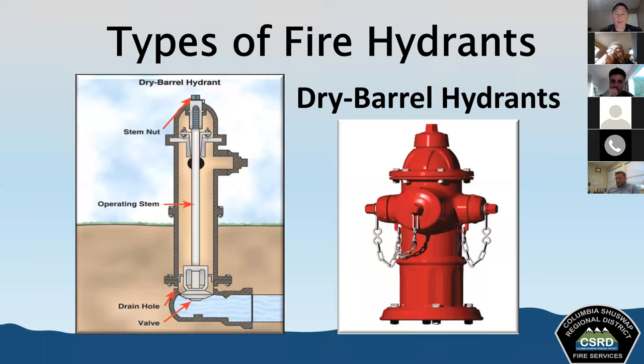We want to hear that water draining out, and we want to give that water time to drain out before we put the cap on. If we put the caps on too quickly, it's going to create a vacuum inside of the hydrant. And that vacuum is going to make it much more difficult for the next person who comes and tries to open that hydrant up. And that might waste us valuable seconds or minutes when we're in the middle of fighting a structure fire.